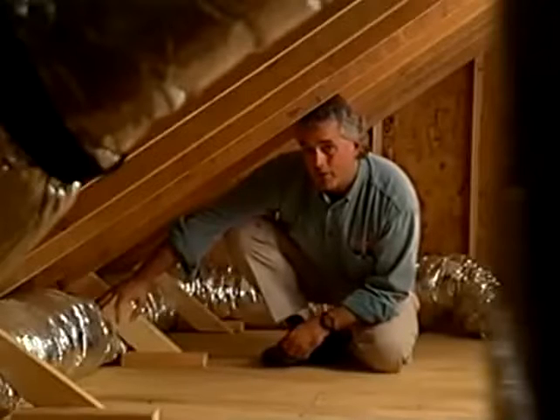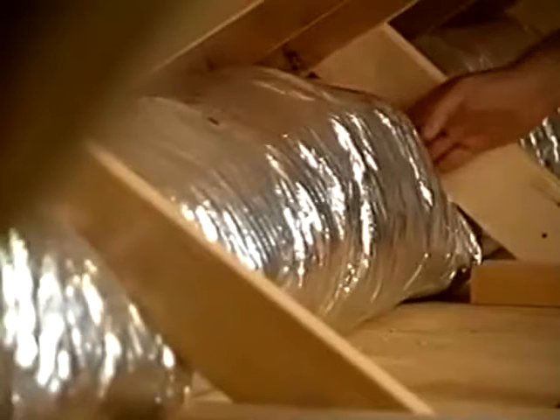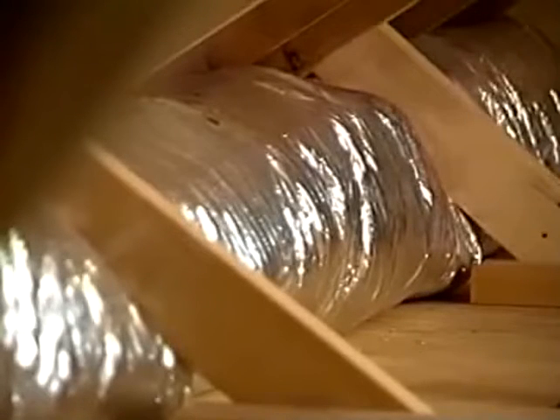The problem that we have in this installation is that by putting this ductwork behind this bracing, it's created constrictions all the way along the supply run. We designed the system for 8-inch duct, and the constrictions that we have is 6 or 7-inch duct, and that's not what we're designed for. We want to make sure that the system is operating as it was designed and as we intended, so we can maximize the comfort for the homeowner.